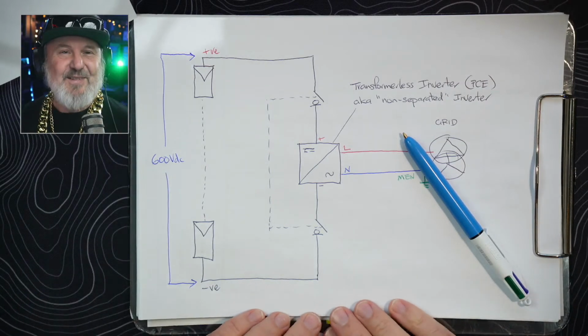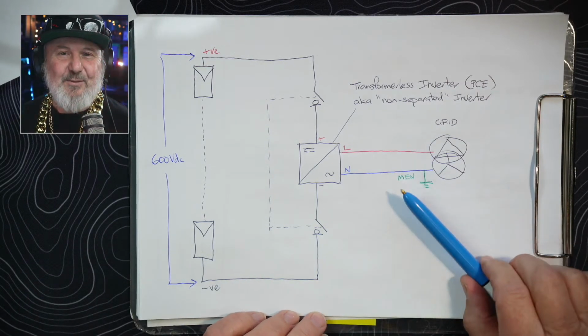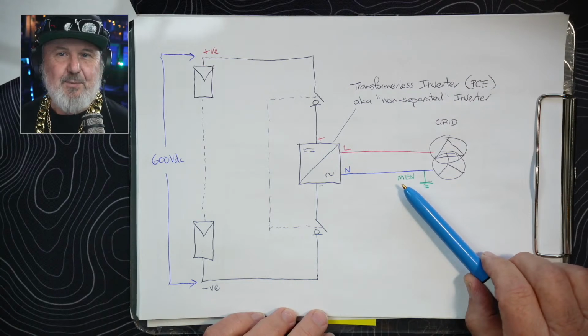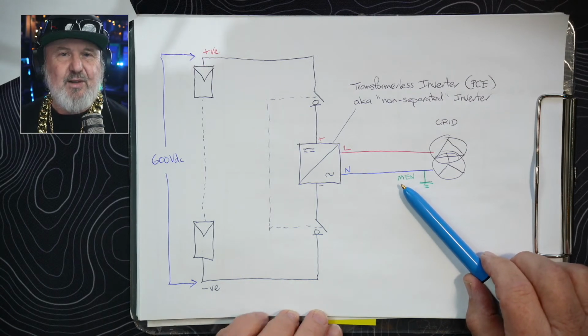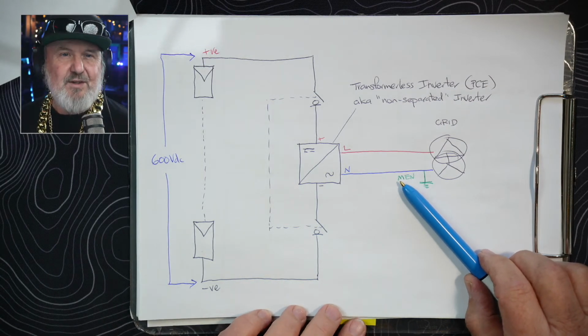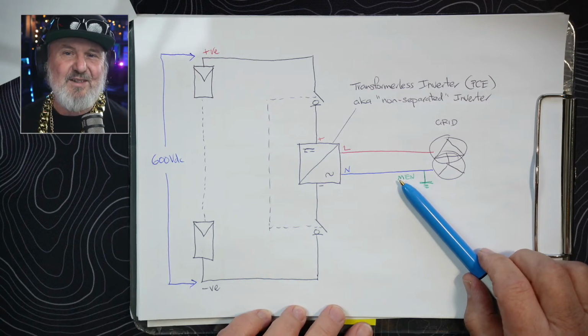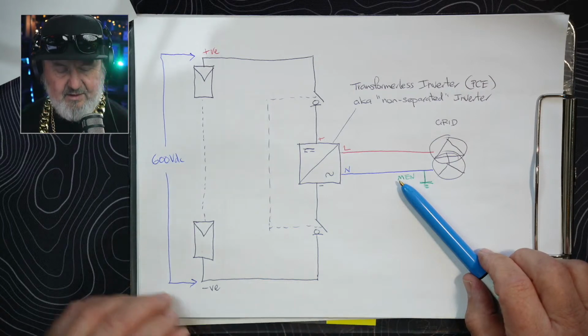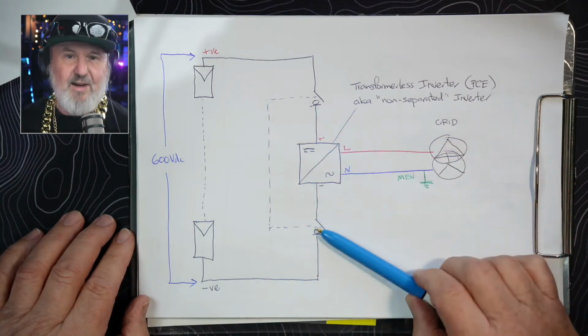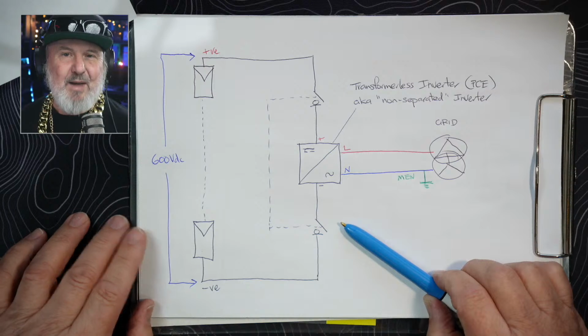Cool. Yeah, so when it comes to non-separated inverters, we're relying on some inbuilt safety features such as earth fault detection and earth fault alarms in case of a problem. But this is where this switching arrangement is impacted.